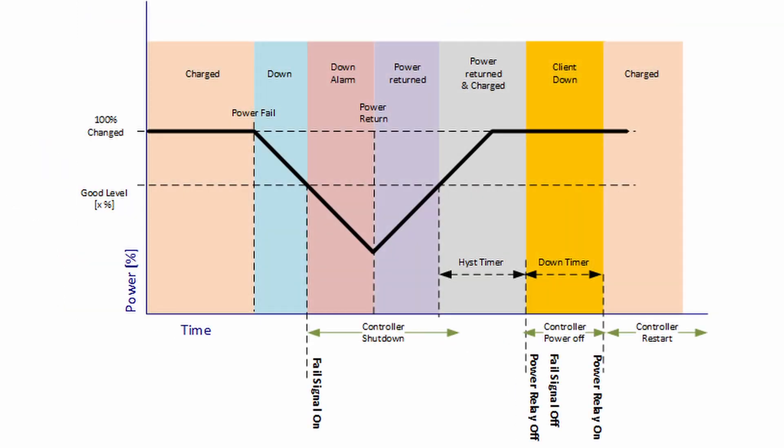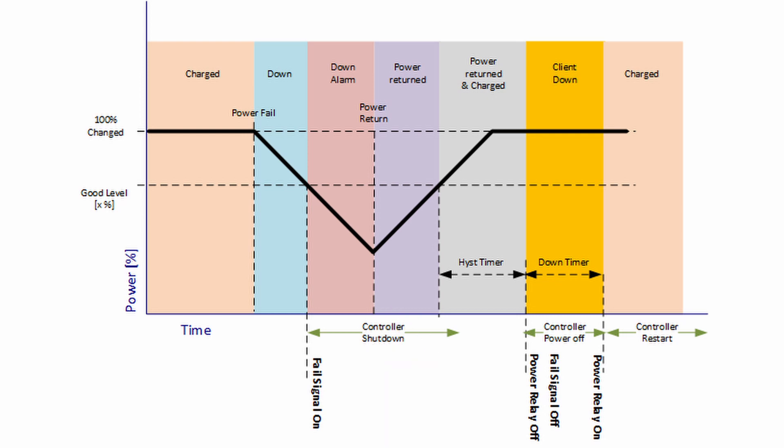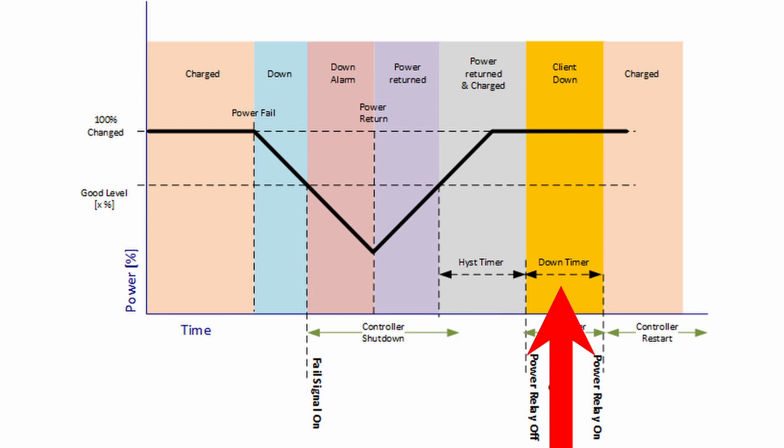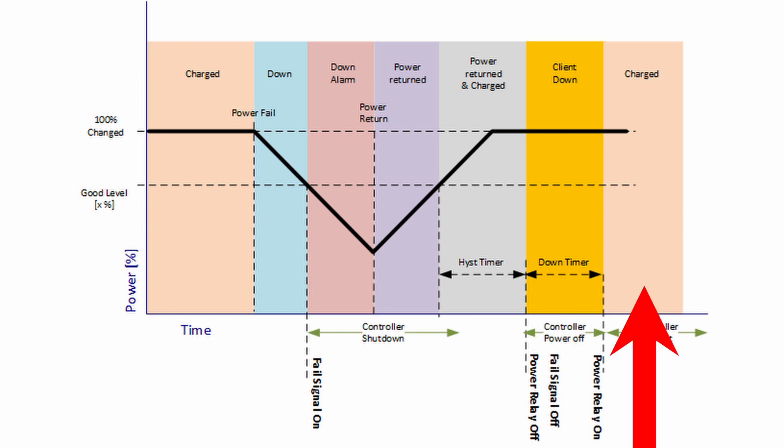If the power returns after a client is informed to shutdown, the UPS will first wait for the charge level to increase to more than the good level. It will also leave some extra time for the client to fully shutdown. Afterwards, the power to the client will be cut and returned to initiate an automatic restart.